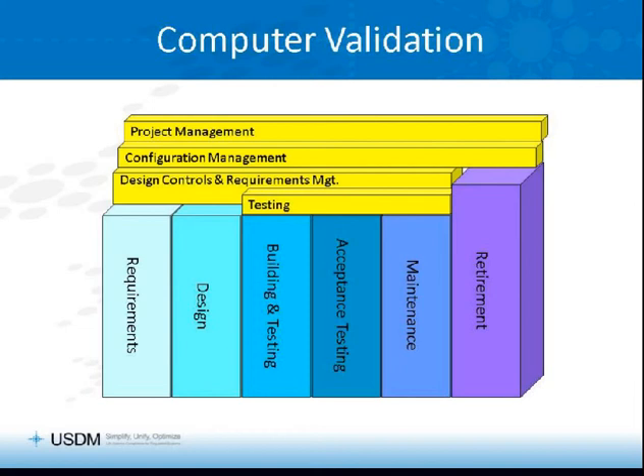A lot of the acceptance testing comes at the end, right before go-live. And if you've got a drop-dead go-live date handed to you by management, and any of those requirement, design, or build-and-test phases take too long, you're shrinking the size of that acceptance testing block on the timeline, until pretty soon you have no time at all, and people are trying to get you to hustle very quickly through formal validation testing. That's never a good thing to do, and I encourage you all to push back on that as much as you can without losing your jobs.